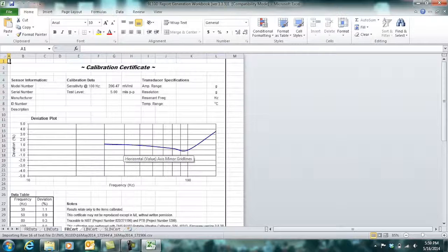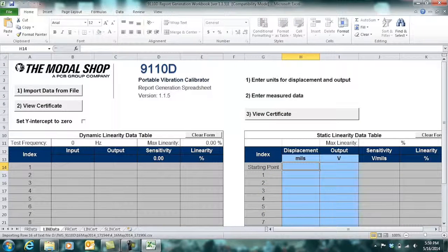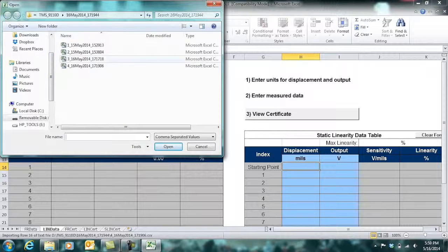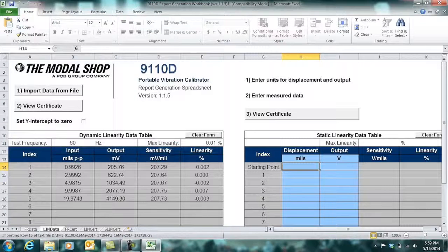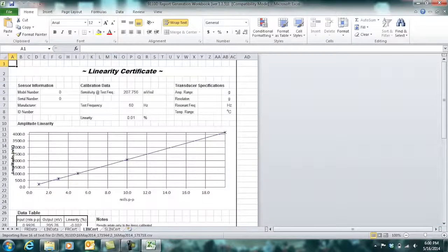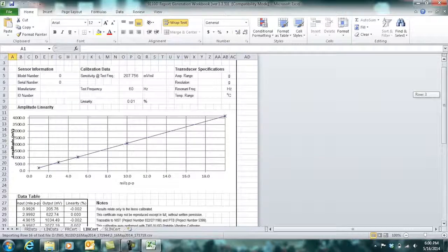Let's also create our amplitude response certificate. Click Linear Data, Import Data from File. I will choose my linearity plot here, which was the third record that I saved. There you see our output, our sensitivity in millivolts per mil, and our output in millivolts increasing as our input increased. And let's view the certificate. And there's a nice look at our linearity plot and our calculated linearity.